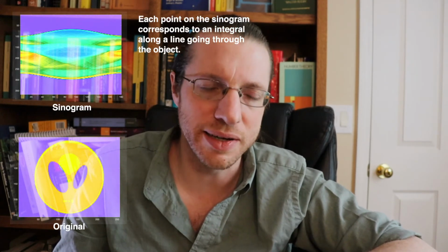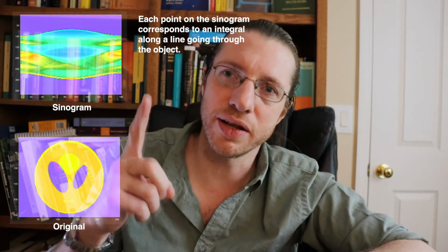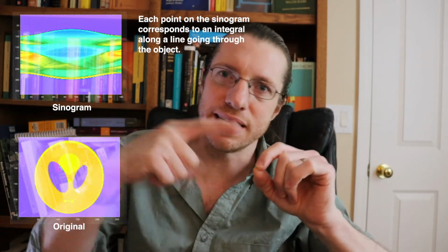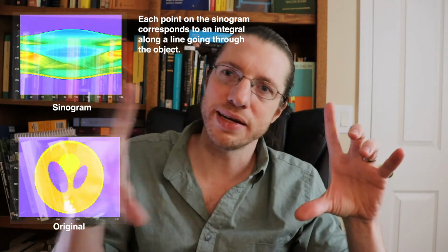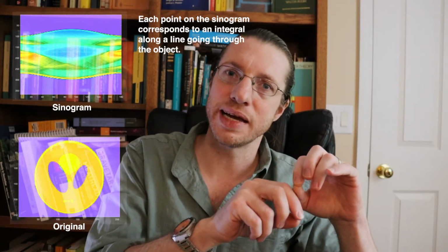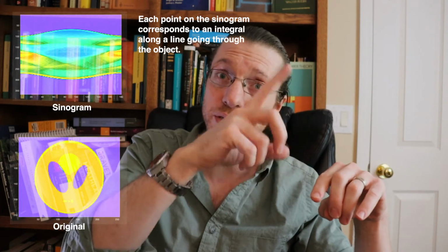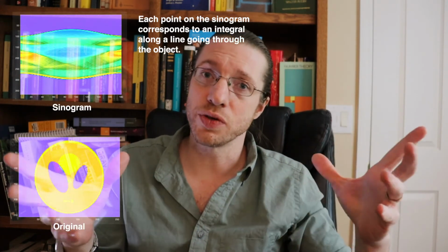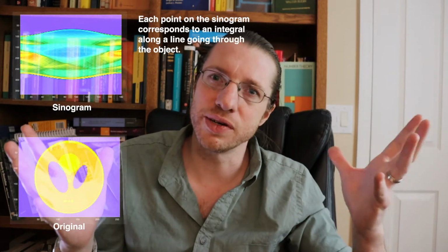For any line, we basically have an initial point and an angle. We're going to plot over the angles and then over the initial position, and between these two quantities you get a sort of polar graph of an object, or of integrals of that object. If you have a little dot or a circle, you basically see something that looks like a sinusoid as you go through. A sinogram is more or less what you're going to get out of an X-ray machine.